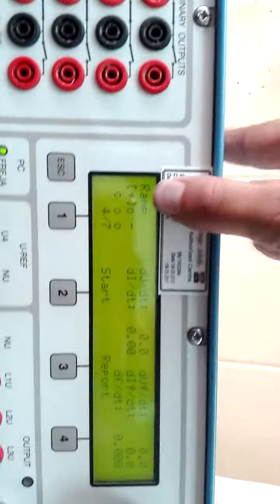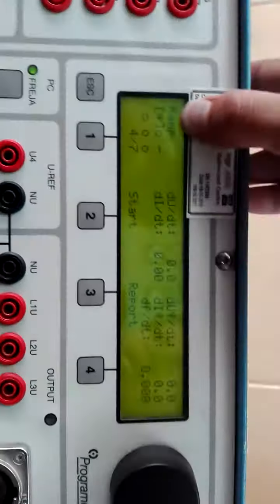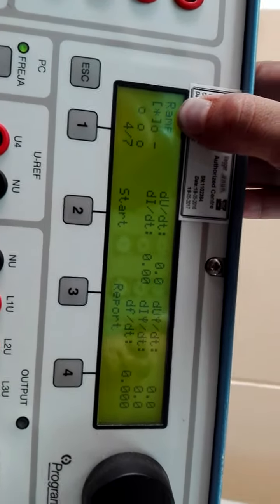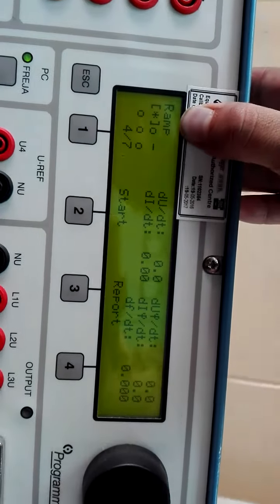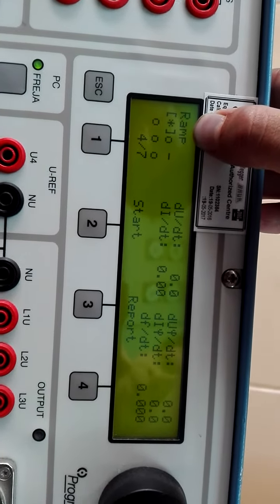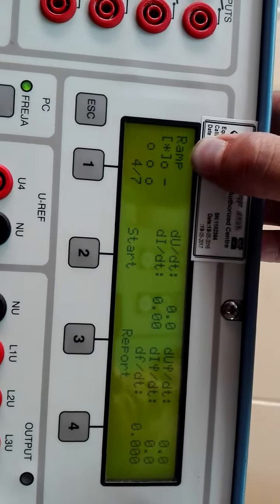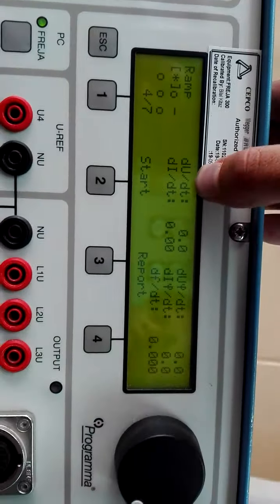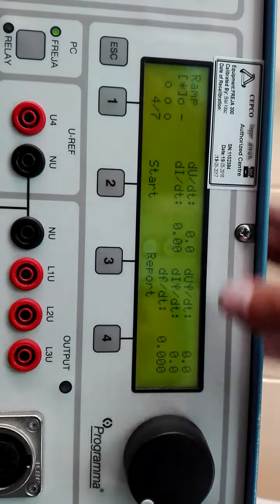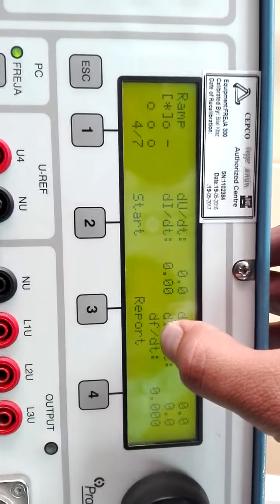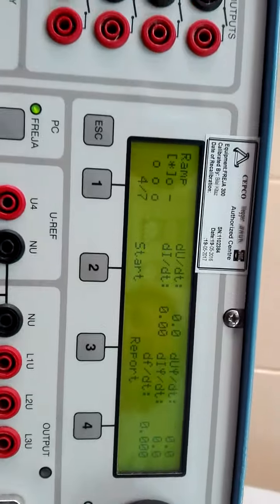Here you can see this page is used only for making ramps, between the set values of page 1 and page number 2. It will make a ramp with respect to voltage, with respect to current, with respect to phase angle of voltage, with respect to phase angle of current, and similarly with respect to frequency. Now here you have to keep this point in mind: by selecting this, the changes will be made per second. So here I will show you with an example.